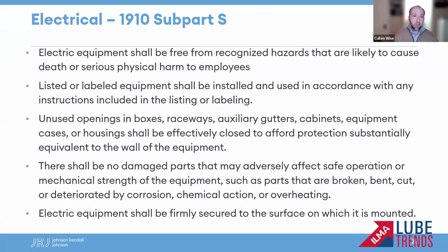Another requirement from OSHA: unused openings in boxes, raceways, auxiliary gutters, cabinets, equipment cases, or housings have to be effectively closed to afford protection substantially equivalent to the wall of the equipment. So in other words, we cannot have any exposures of live electrical. We can't have any openings in enclosures or our equipment. Another very common example here is if you open a breaker panel and there's an unused slot in a breaker panel and there's no cover, there's no blank over it, so then you just have a gap there. That's something that would fall under this requirement.